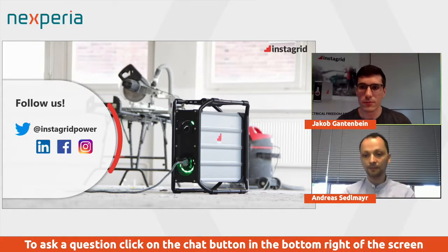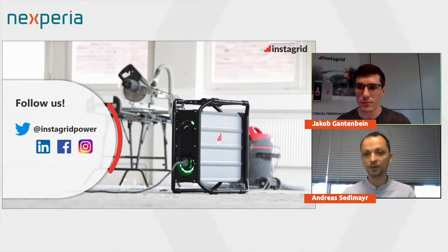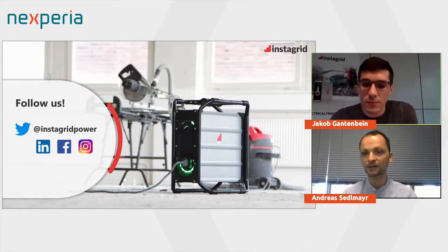And the second thing is certainly we can do balancing quite easily. We can do active balancing between the modules because this is what you get for free with the architecture. You can decide when to switch in which module based on temperature, based on voltage, and that makes it quite easy for active balancing within the modules. Of course, passive balancing is more than enough because it's only 6 series cells. And we have a lot of experience in that and know that they are not drifting too much within that small cluster.